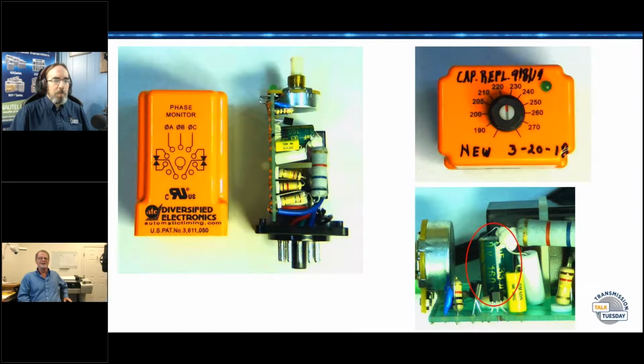One of the things you run into is you don't know how long those parts have been sitting on the shelf before you get them. It's one of those things where you think, well, I'm ordering one, I'll order five. But the downside of stocking and keeping electrolytic capacitors on the shelf is that manufacturers rate a lot of them for 10 to 12 years of shelf life, even when they're not being used. So if it sits on a shelf for 5 years, it's not going to last as long as one that was recently manufactured.